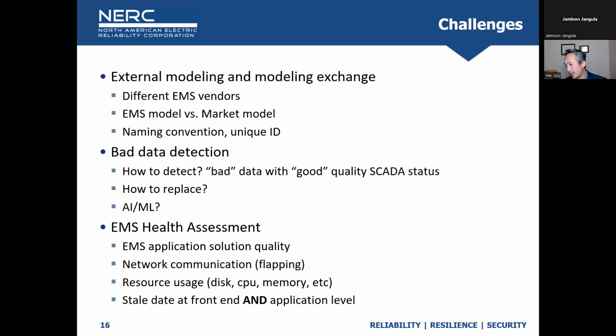The second issue we see manually is bad data detection. Bad data is always present, because you may have noise, breaker failures, or RTU failures causing problems where they send back bad values. For example, a breaker is open, but the measurement on that breaker or line tells you it's 100 megawatts or 100 megavars. So what's going on - is the line open while there's still a measurement there? Which one do you trust: the breaker status or the analog measurements?